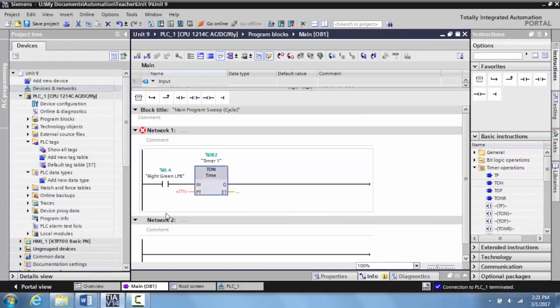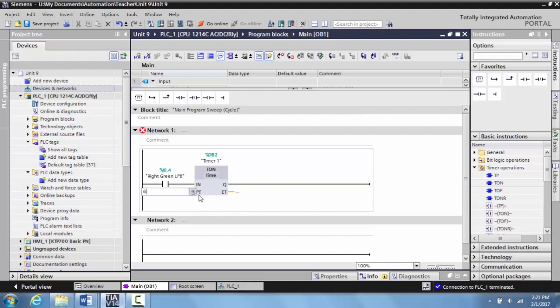We want this preset timer to be for six seconds. Whatever value you type into PT, which is your preset time, that is multiplied by one millisecond. So if you want a six second on delay, you type in 6000 and you hit enter. You'll see here that it actually says six seconds.